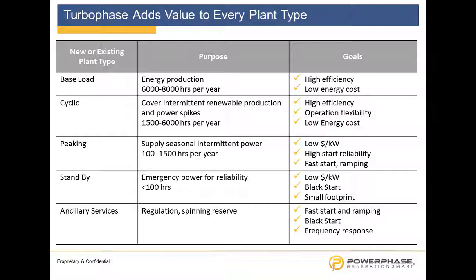And then ultimately, ancillary services here in the state specifically, the regulation, meaning frequency response up and down. Turbophase is very quick. We can change the power into the gas turbine as fast as we can move a control valve and as fast as the gas turbine's fuel system can respond. And so with that, we're able to be put into an AGC mode, an automatic grid control mode, and let Turbophase just follow a grid demand signal. That allows the gas turbines to stay fixed at base load and allow the Turbophase modules just to move the air production up and down.